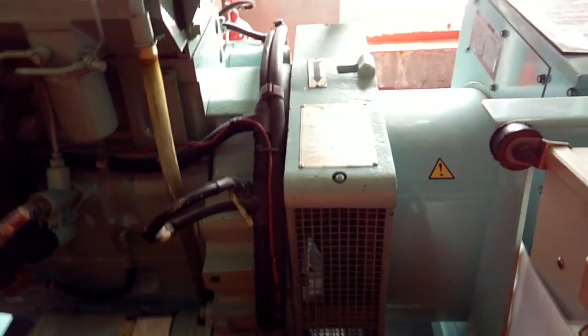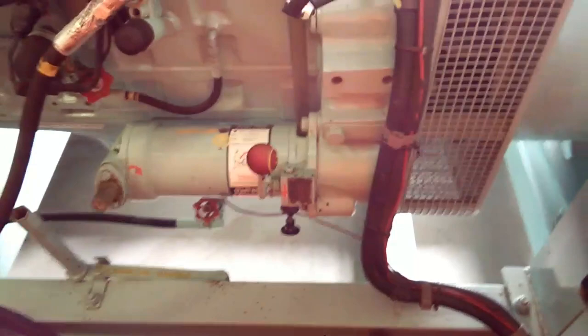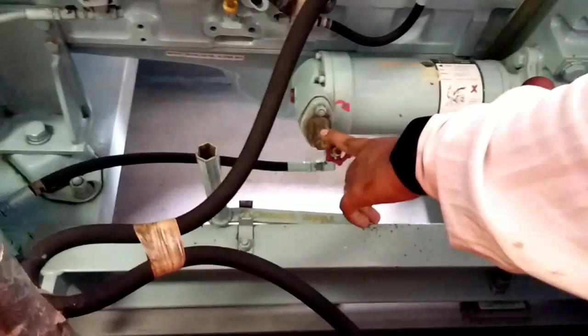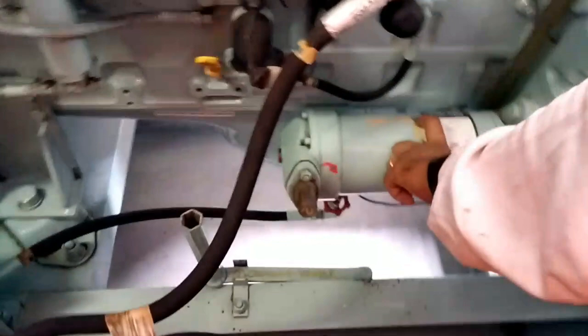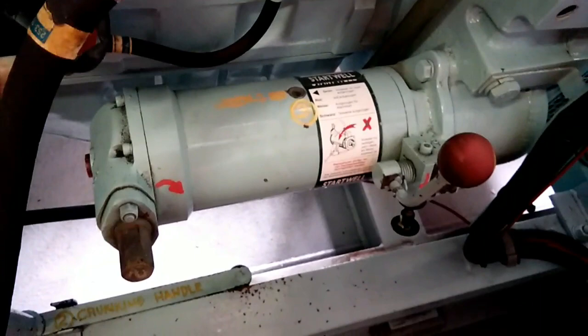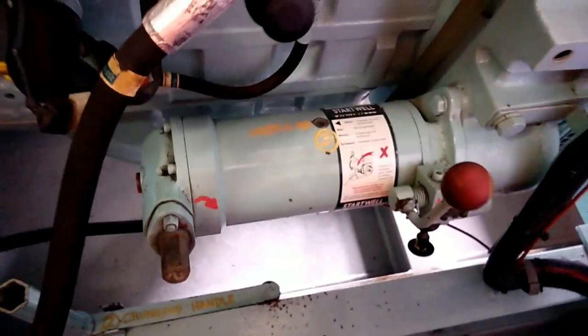The second mode: here you are having a spring. You will have one handle — a cranking handle it is called. You put the handle and keep turning. Here there is a small window; you have to keep turning until the indicator becomes red. Right now I think it is green, so you have to keep turning until it becomes red.